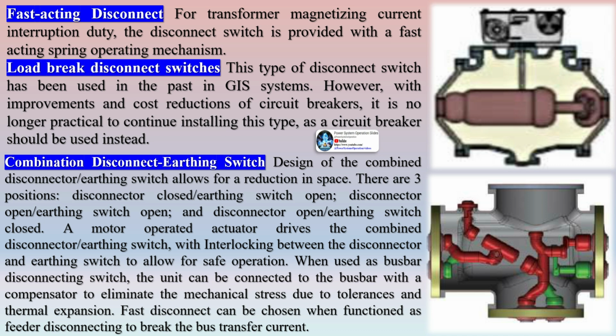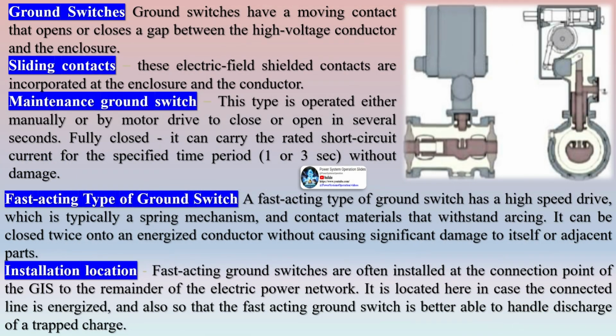Load break disconnect switches. This type of disconnect switch has been used in the past in GIS systems. However, with improvements and cost reductions of circuit breakers, it is no longer practical to continue installing this type, as a circuit breaker should be used instead.